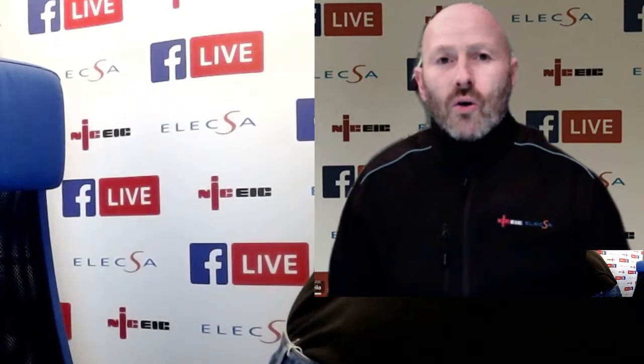Yes, we can, Sam. Obviously, not everything is plain and simple and black and white. There's compliance to consider as well. But section 701 does list ventilation equipment as part of the current using equipment that can be installed in zone 1 of a bathroom. There are additional requirements that we do need to consider. The IP rating, minimum of IPX4 within zone 1, and if there is a likelihood of cleaning with jets, then minimum of IPX5 for cleaning purposes. We also need to consider manufacturer's instructions, to ensure that the equipment in question is suitable for zone 1. So it's always good to make contact with them or have a look at any material that is provided with the ventilation equipment.